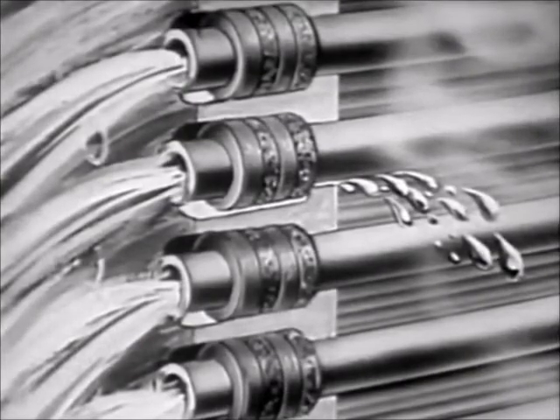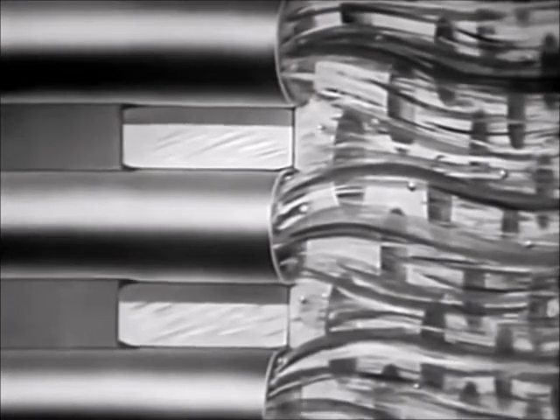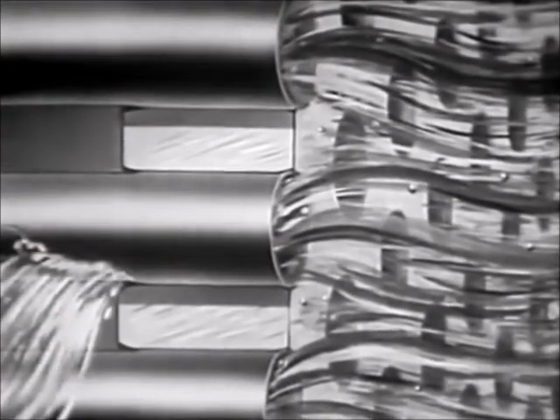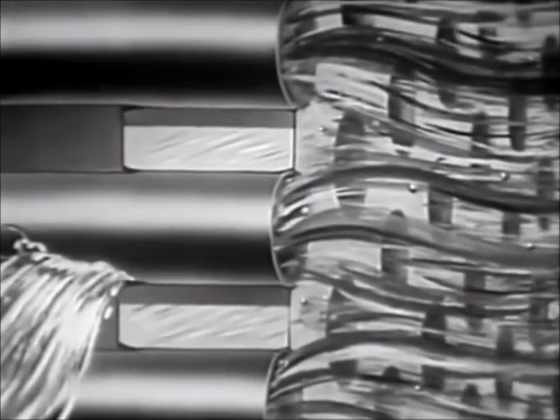Defective packed joints are another source of leaks. Leaks may also occur in the tubes. One cause of tube failure is an expanded joint that has been expanded too much. The tube is weakened and likely to split. A split can also be caused by twisting a tube while making the expanded joint.